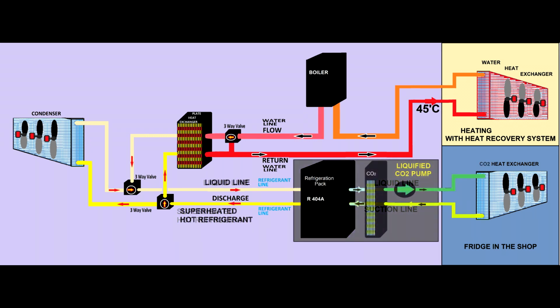Before I go further, I have to let you know that there are many types of methods to keep the product cool in a store, and you have to be very careful with this heat recovery system sometimes, because if the software is not correctly written, or if the valves are bypassed, you might lower the refrigerant pressure and you might not have a refrigeration process. Especially in this case, you have to pay attention.